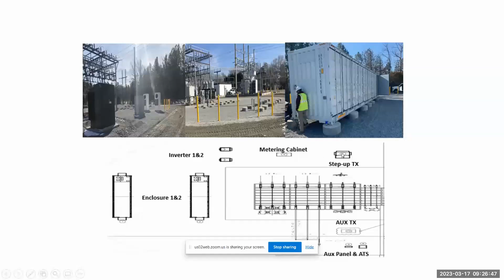Then I leave the metering cabinet and go to a step-up transformer. The reason the step-up transformer is there is to convert the power to the voltage levels needed to inject back onto the grid. So I'm leaving the batteries at 1,000 volts DC, inverting that to become 480 volts AC, and then that 480 volts AC gets stepped up to 34,500 volts to get injected back out onto the grid.